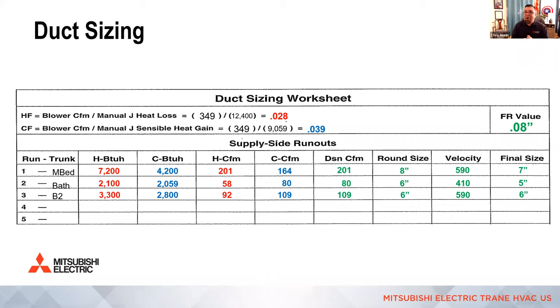Steve asked, he says that he has an honest question here. Why not size directly to feet per minute instead of doing the friction rate method and then changing it for feet per minute? Well, that's because you're going to have a tough time accounting for all your pressure drops, right? So if you size only for velocity and you don't account for pressure drop in the friction rate piece, it's just assuming that all your friction rates are fine, right? So in this example, I could do this by velocity only, but then find out, oh my gosh, I have so many pressure drops that the system doesn't work. I need to have something available to overcome, right?